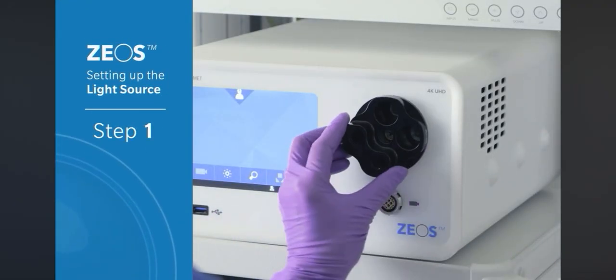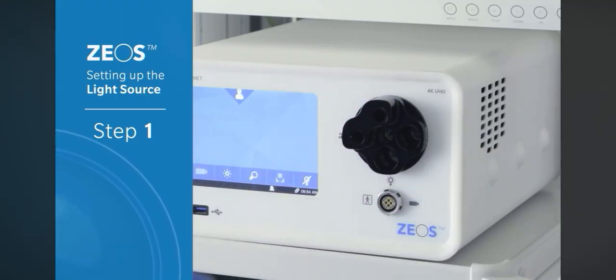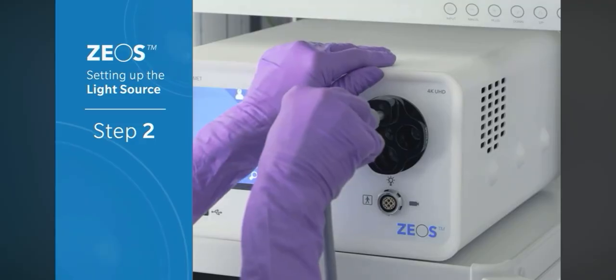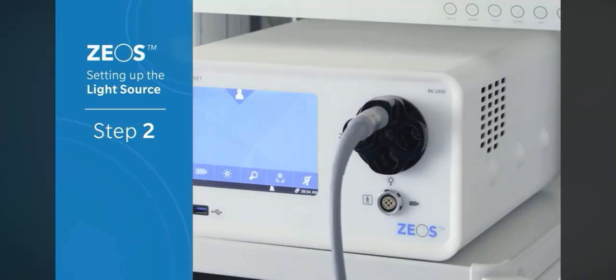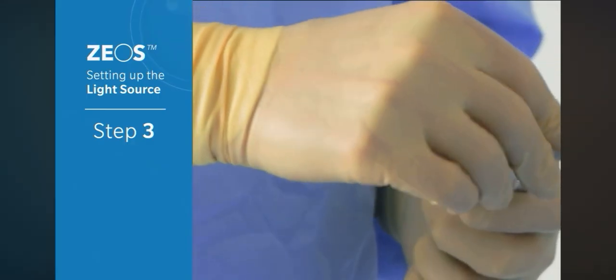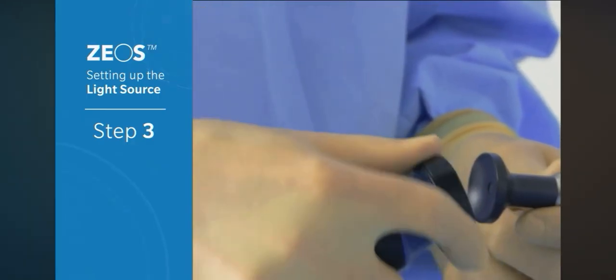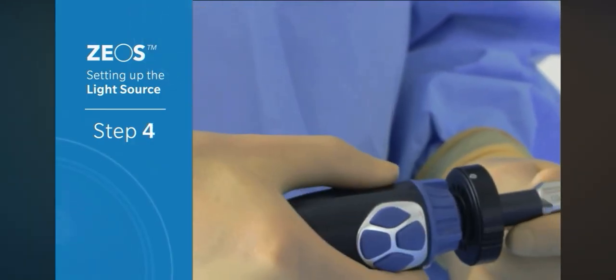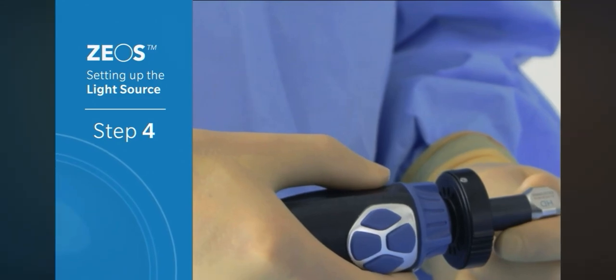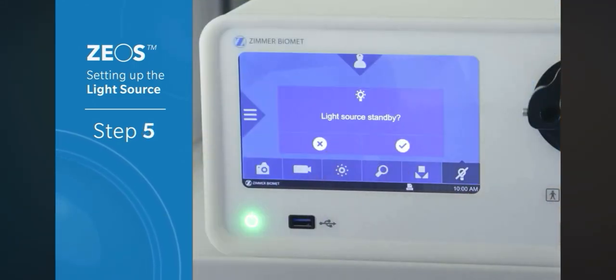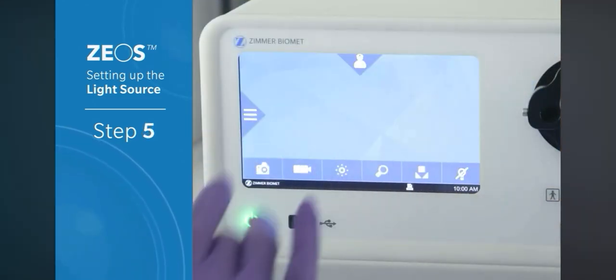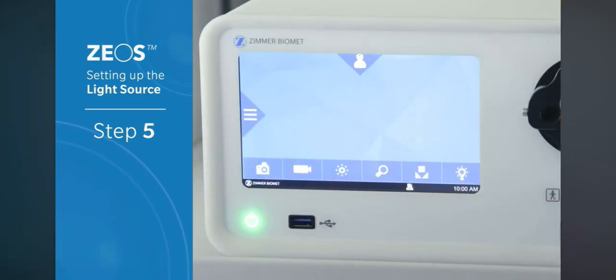Rotate the light source turret with the appropriate light guide receptacle at 12 o'clock. Insert the light guide cable into the light guide receptacle on the front panel of the console. Attach the other end of the light guide cable to the scope. Attach the scope to the camera head grabber. Press the light source on standby button to on to activate the LED light engine.